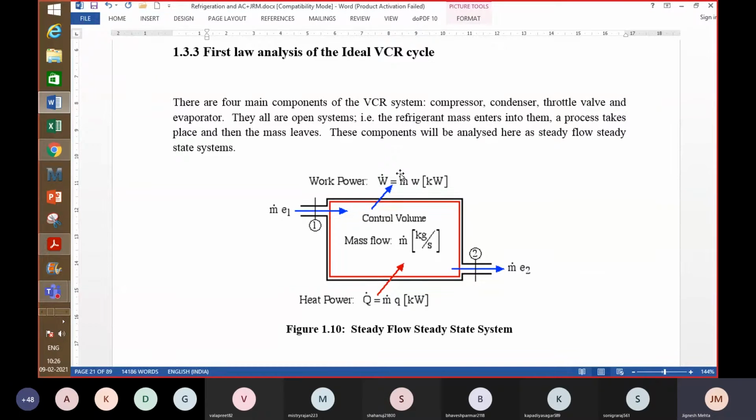We would like to get that. Another important parameter is the energy performance or the COP of the system, because you are consuming some power, and by consuming that, what is the cooling rate that you produce? The ratio of those two is the COP of the performance. It's always desirable that with the same amount of power consumption, you can build a system which can provide a high rate of cooling.